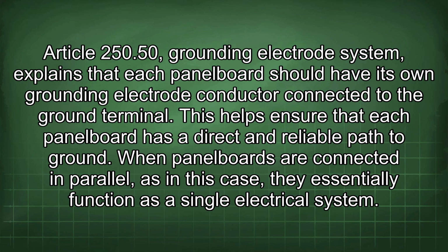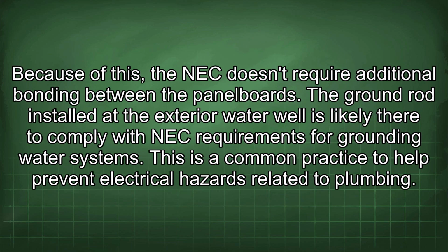When panel boards are connected in parallel, as in this case, they essentially function as a single electrical system. Because of this, the NEC doesn't require additional bonding between the panel boards. The ground rod installed at the exterior water well is likely there to comply with NEC requirements for grounding water systems. This is a common practice to help prevent electrical hazards related to plumbing.